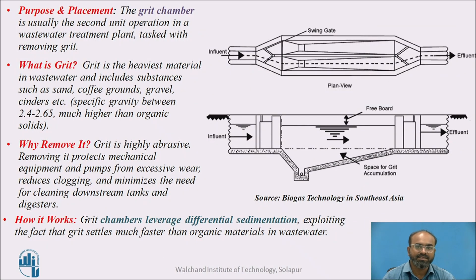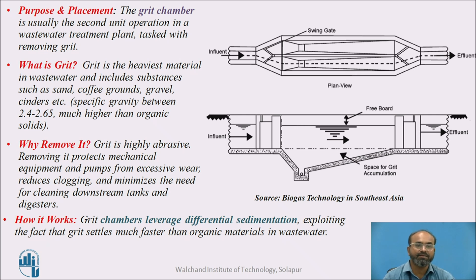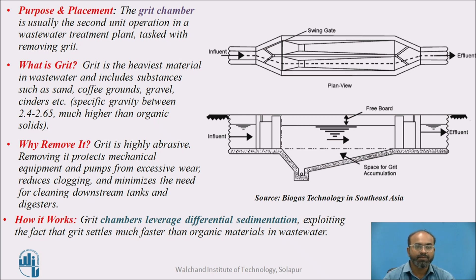First of all, let us see what is a grit chamber and why it is needed. A grit chamber is usually a secondary unit operation after screening in a wastewater treatment plant, tasked basically to remove grit. Grit is the heaviest material in wastewater, which includes various substances like sand, coffee grounds, gravel, cinders — materials having a specific gravity between 2.4 to 2.65 — and they are very much heavier than organic material.